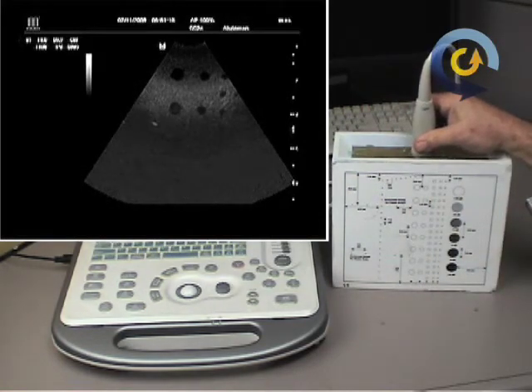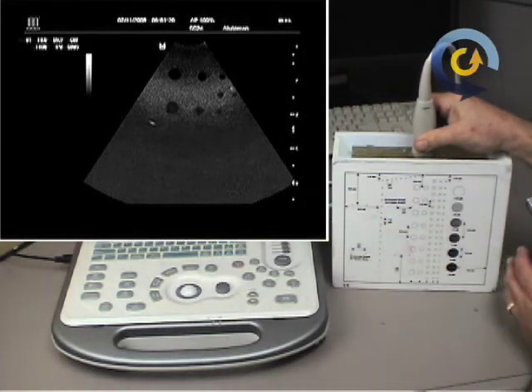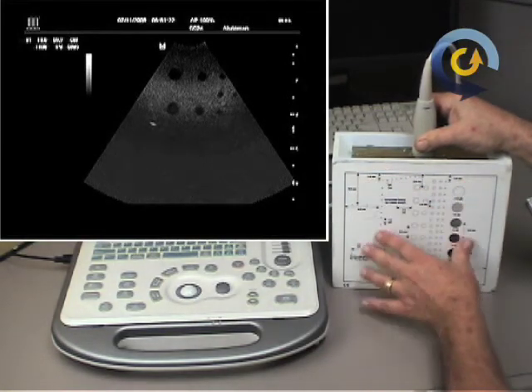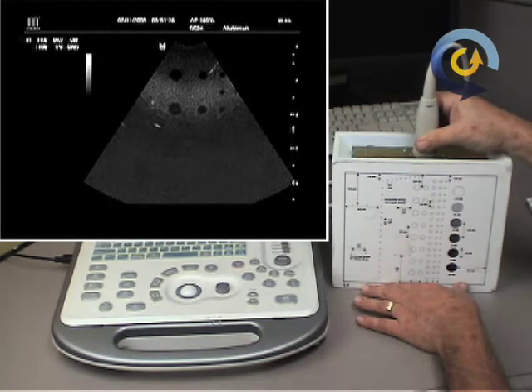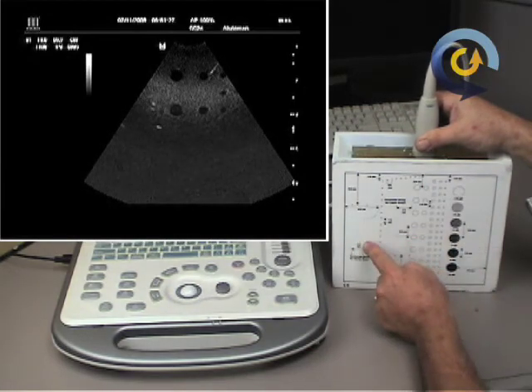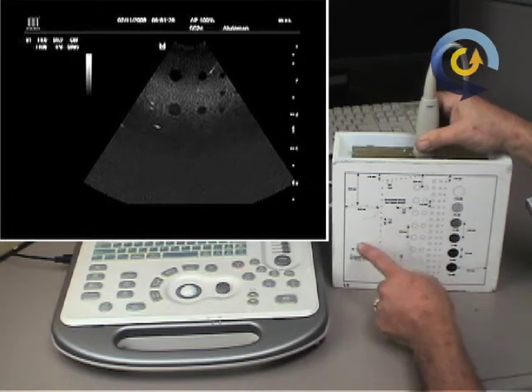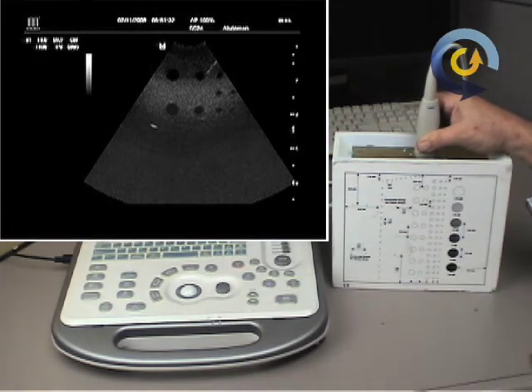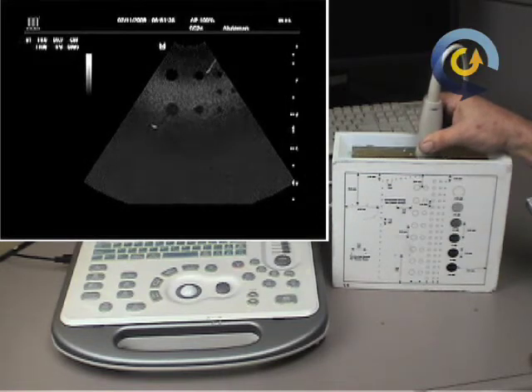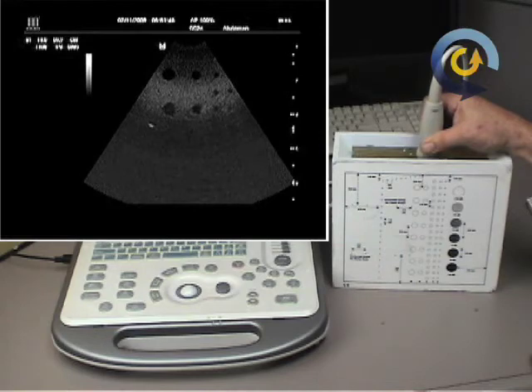One of them is called a string phantom, and it literally is a block of water. It has some material inside that is roughly the acoustic properties of blood, and it has a moving string that has small beads on it. And because of that, it can measure the motion, and it can actually verify that you've got the correct frequency scanning for your Doppler, and it will even do color and show that it's got the right frequency. Those are much more uncommon because they're very expensive, and they typically would just be in a good lab that had a reason to test that. Most of the Doppler verification is actually done electronically now, where it can inject a frequency and measure it back.